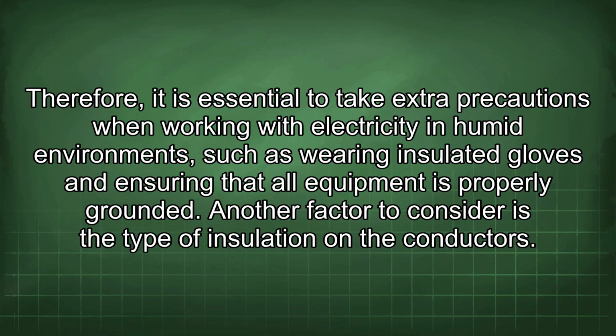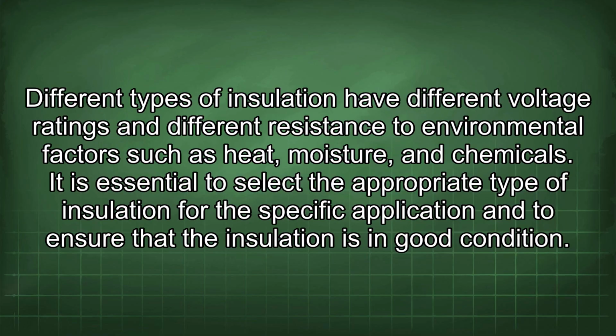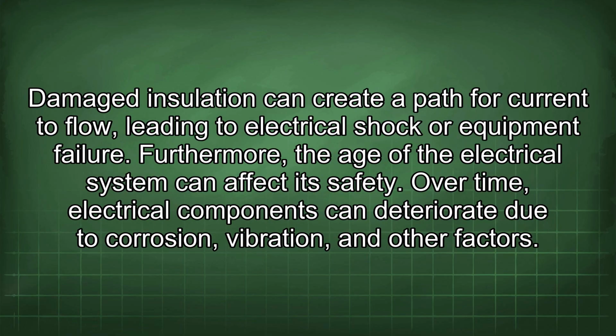Another factor to consider is the type of insulation on the conductors. Different types of insulation have different voltage ratings and different resistance to environmental factors such as heat, moisture, and chemicals. It is essential to select the appropriate type of insulation for the specific application and to ensure that the insulation is in good condition. Damaged insulation can create a path for current to flow, leading to electrical shock or equipment failure. Furthermore, the age of the electrical system could affect its safety.